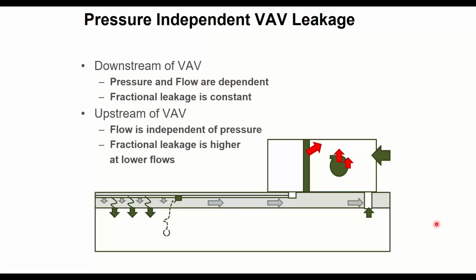On VAV systems, we kind of divide the problem in two halves. For those of you that are familiar with VAV, you probably know that upstream of the VAV terminal, the zone dampers, upstream is typically a medium pressure duct system, and downstream is a lower pressure duct system. Duct leakage penalties are larger the higher the pressure you operate at is, right? Because then a small hole can have a giant amount of leakage, CFM-wise, because the pressure pushing it out the hole is more. So sealing duct systems upstream of the VAV box is significantly more important than sealing them downstream of the VAV box. Should you seal downstream? Yes, you should do that. But if your budget doesn't afford that, or if the downstream sections are inaccessible, at least seal up all the main duct runs and you'll have an improved system.